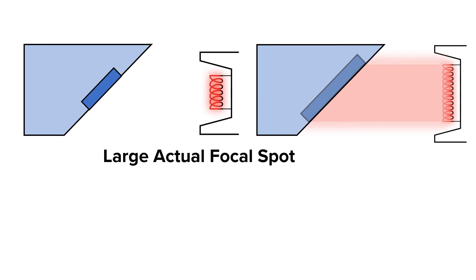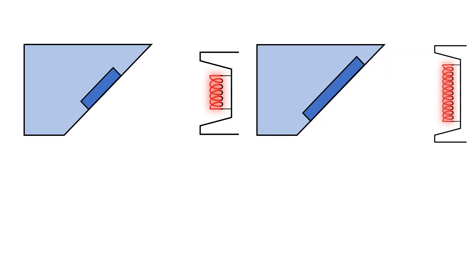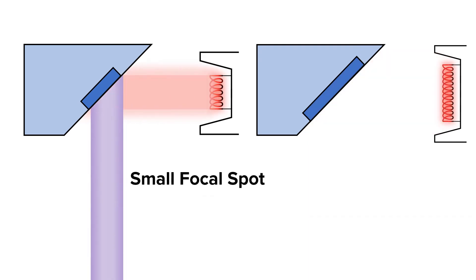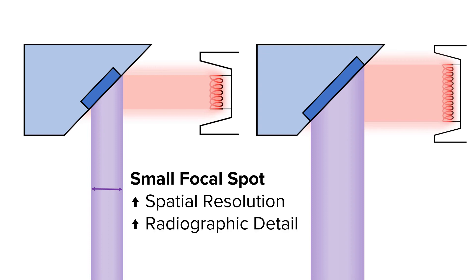The large actual focal spot also has a handful of pros and cons. A few pros of the large actual focal spot are that it is great at dissipating heat because more of the anode surface is being used, it is good at imaging thick body parts, and it is good when you need to use a short exposure time. However, a con of a large actual focal spot is that it produces a large effective focal spot. The huge benefit of a small effective focal spot is an increase in spatial resolution and thus greater detail.